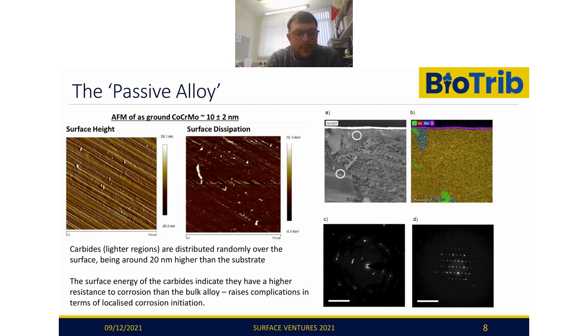Essentially this passive film is like a thin ceramic film on a surface, kind of akin to a piece of chewing gum. What you have is a very, very thin protective layer on a surface that is on top of a quite soft, quite ductile metallic surface. And so any mechanical stresses, any tribological shear, any abrasion or any fatigue will disrupt this oxide film and expose a bulk surface, which is very reactive in nature due to the alloying elements that are there. It interacts with the biological environment, which then ultimately leads to enhanced corrosion.